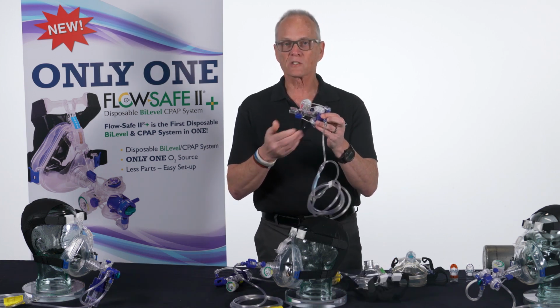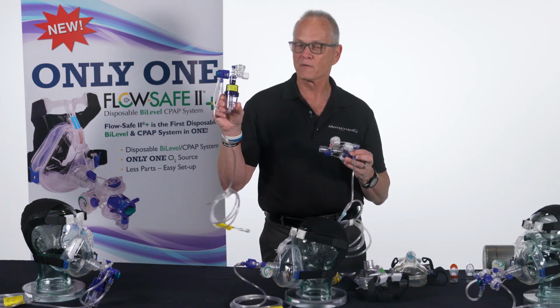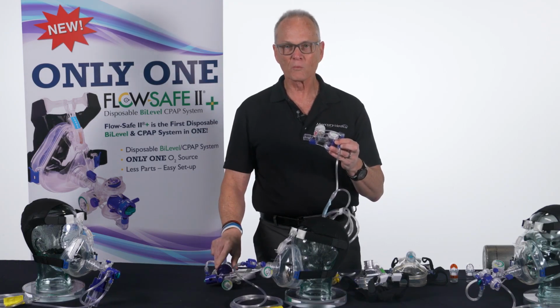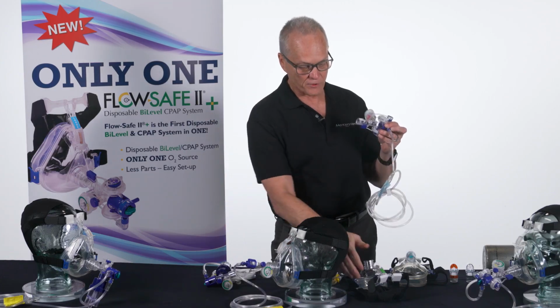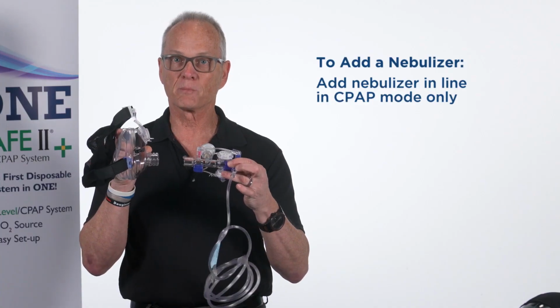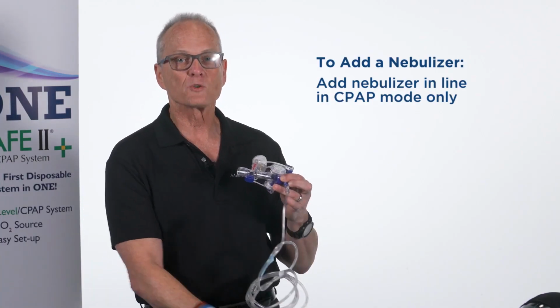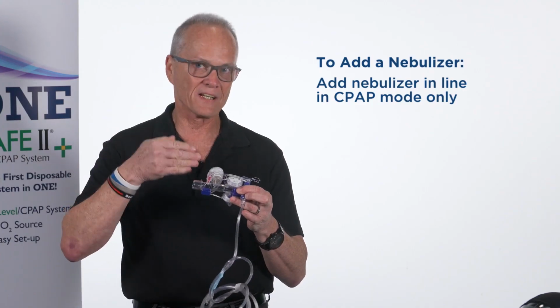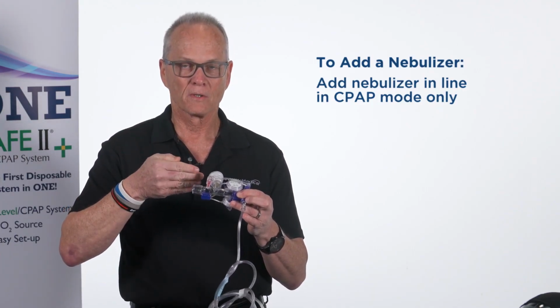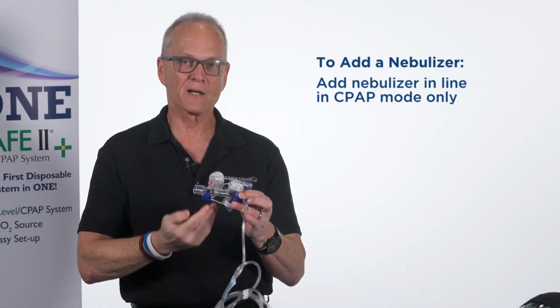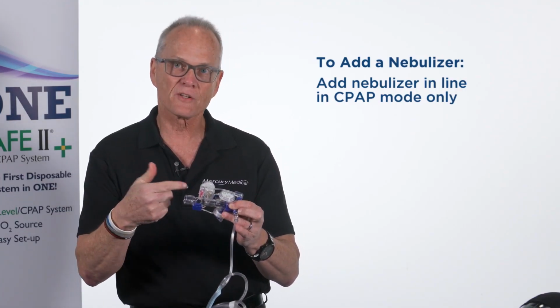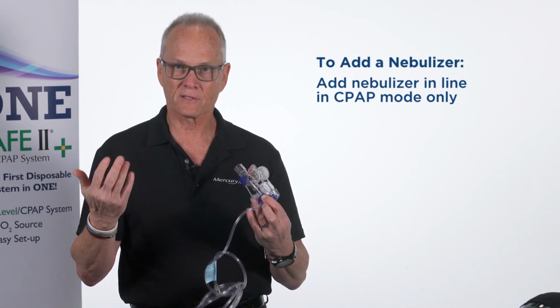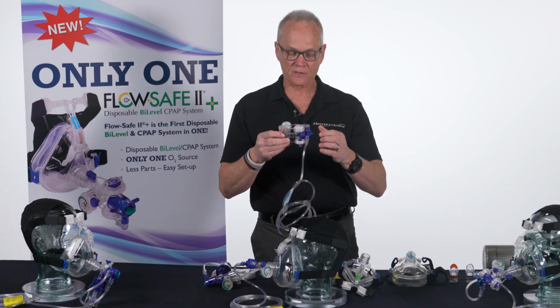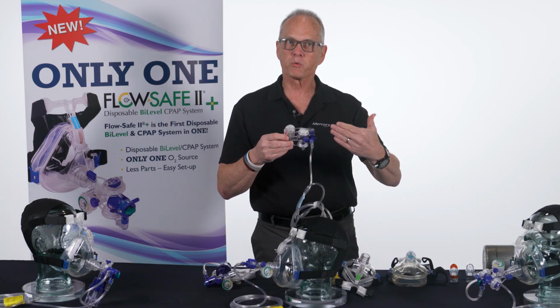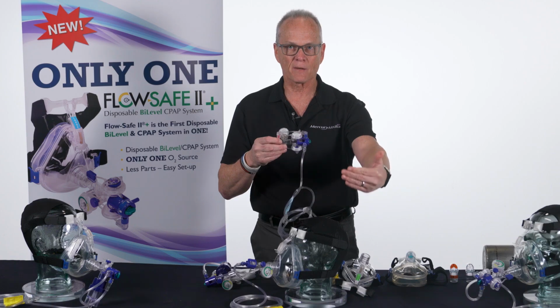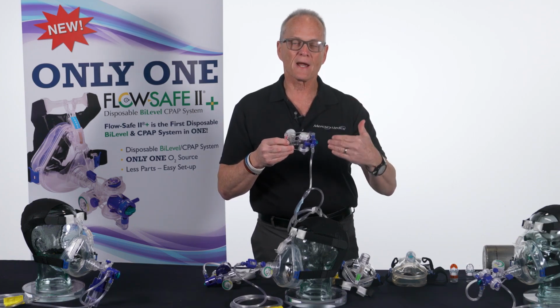Now you'll notice that it does not have an integrated nebulizer like a FlowSafe2EZ. The only way to do a breathing treatment or a nebulizer treatment, you would have to do it like a FlowSafe2 and put a T-piece in between and do your nebulizer that way. But you can only give a breathing treatment while it's in the CPAP mode. If you add the extra flow from a nebulizer while it's in the BiLevel mode, it kind of tricks the device and it won't function as it's needed. As you do this, and we're going to demonstrate this in just a few minutes, it's very important that you follow some exact steps or the device will not function as designed.